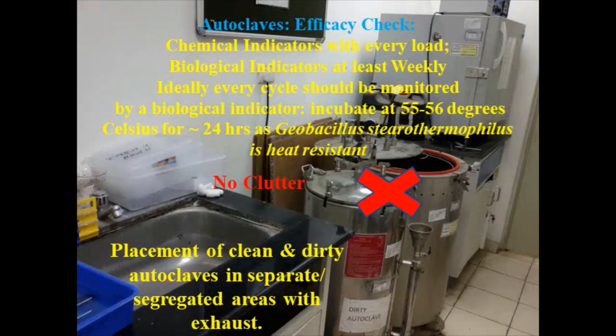Ideally, every cycle should be monitored by a biological indicator, which is usually done in the CSSDs, but to reduce the cost, these biological indicators are costly. So at least once every week, that is the recommendation for use of the biological indicators for the clean and dirty autoclaves, that is the discard autoclaves.